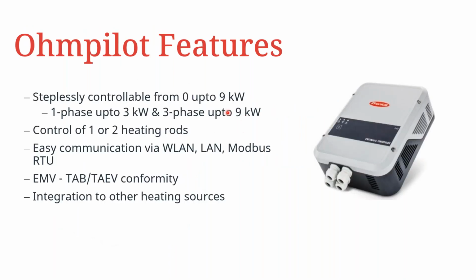The Ohmpilot can control anything from 0 to 9 kilowatt. It can be single-phase or 3-phase. So in single phase up to 3 kilowatt, and then in 3-phase a maximum of 9 kilowatts. You can also do 1 or 2 heating elements, and communication is quite easy. It can be done by LAN, WLAN, or Modbus RTU. So it's also very possible to integrate the Ohmpilot into already existing heating systems, and you're able to retrofit the Ohmpilot to maximize or generate even more hot water for you.